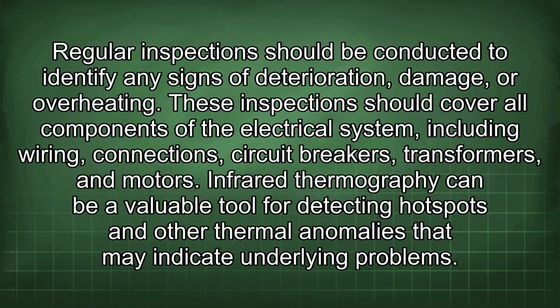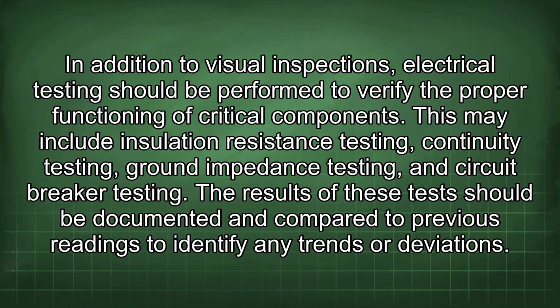Infrared thermography can be a valuable tool for detecting hotspots and other thermal anomalies that may indicate underlying problems. In addition to visual inspections, electrical testing should be performed to verify the proper functioning of critical components. This may include insulation resistance testing, continuity testing, ground impedance testing, and circuit breaker testing. The results of these tests should be documented and compared to previous readings to identify any trends or deviations.